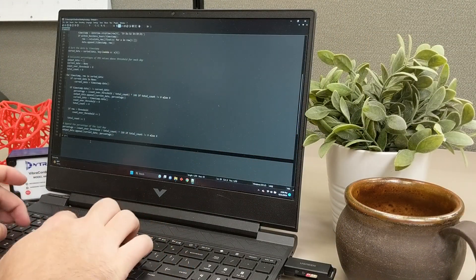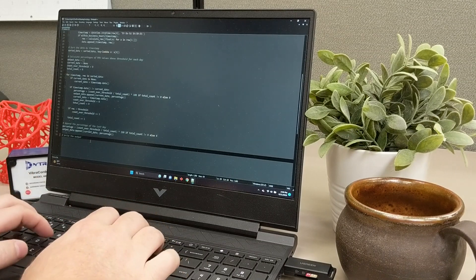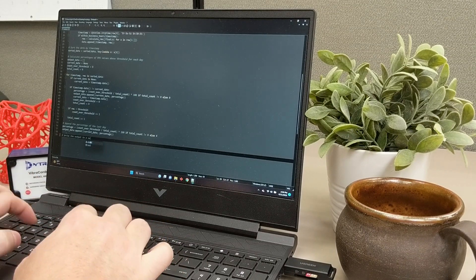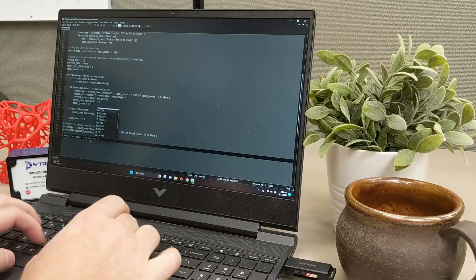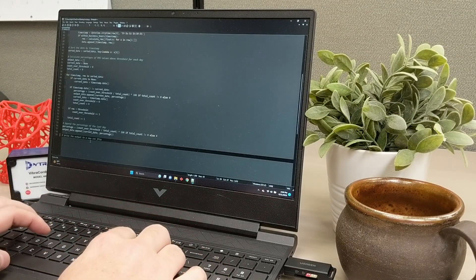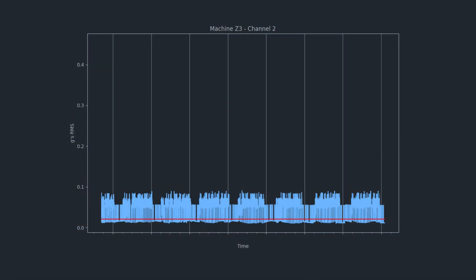To analyze the vibration data, we developed a Python script that converts the vibration data for each channel of the 4600A1 vibrecorder into a root mean square, or RMS. The RMS supplies us with a single value related to the amount of energy within the supplied waveform over a given interval.